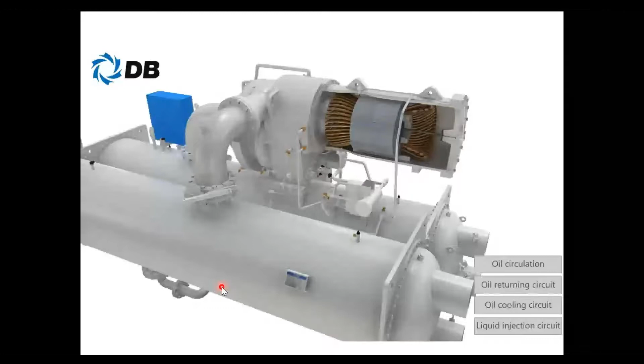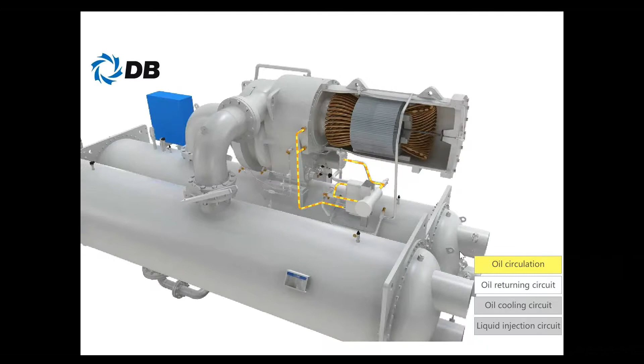I will quickly give you some idea about how different components work. We spoke about the oil pump and oil circulation, and how critical they are. So I'll first talk about the oil circulation. This is the oil pump, and this is how the circulation will look. The oil is being pumped into the bearing, so the bearing stays lubricated and the compressor is able to operate at higher RPM. This is the oil return circuit.